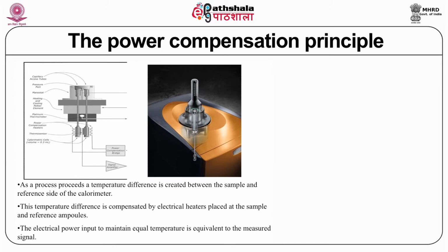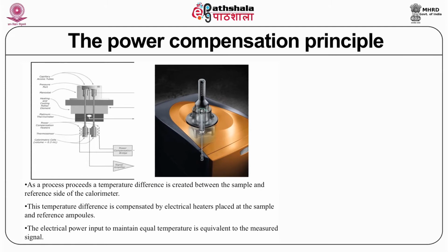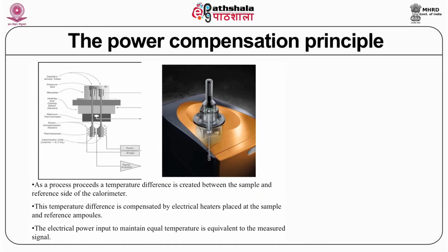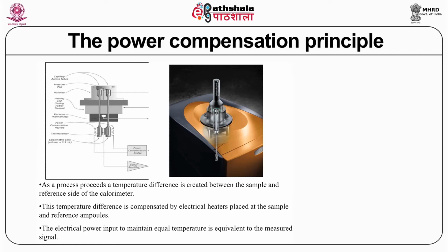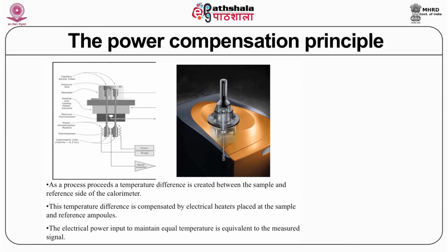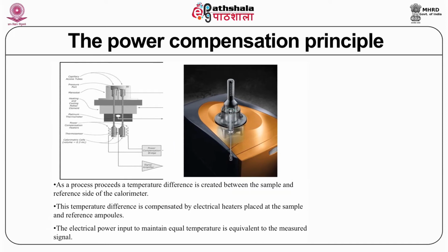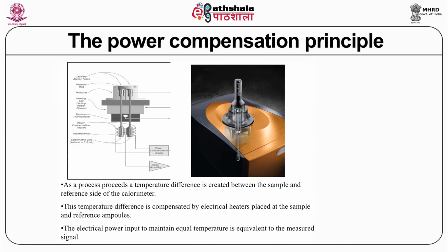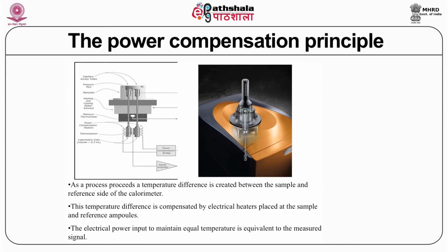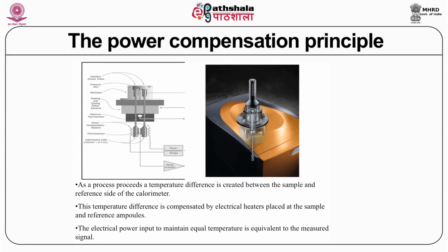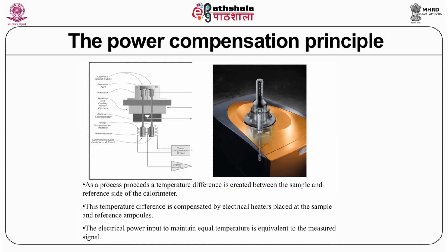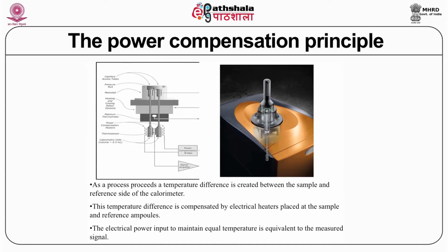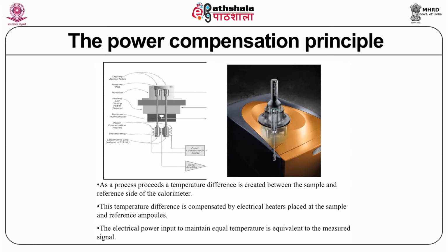This is one of the instruments. There are very few companies that make this ITC, and this is one of them. I do not want to mention the company name, but this is generally what the equipment looks like. These are the different parts: power compensation, platinum thermometer, and then there is a thermostat and a capillary where you put the sample.